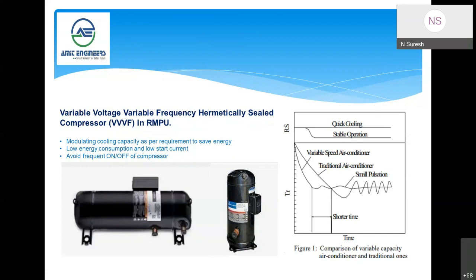Normally it will be running at 50 hertz, and whenever the cooling load is less, it will automatically run at a lesser frequency. So over a period of time, say for example in a day, even for 1 hour or 2 hours, this is only an example I'm saying, practically it will definitely give more energy saving. The power consumption will be reduced by reducing the input power. One more advantage of the variable frequency compressor is that we can avoid the on off.